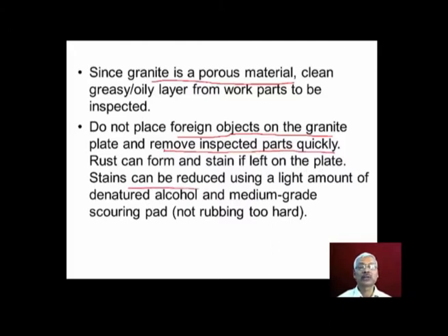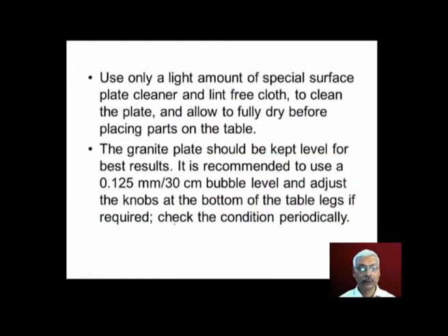Stains can be reduced using a light amount of denatured alcohol and a medium grade scouring pad. We should use only a light amount of special surface plate cleaner and a lint-free cloth to clean the workpiece table surface, and we should allow it to fully dry before placing the parts on the table.